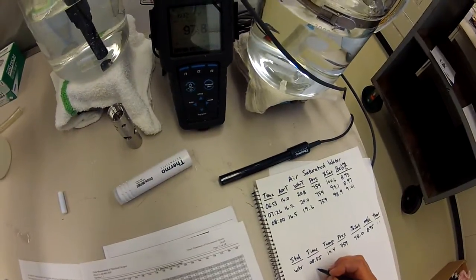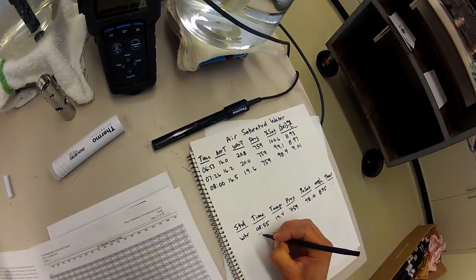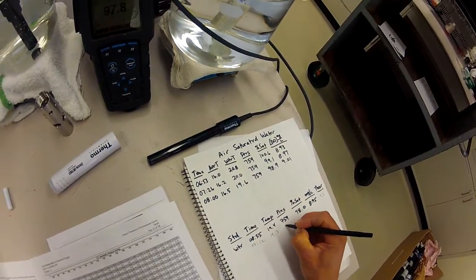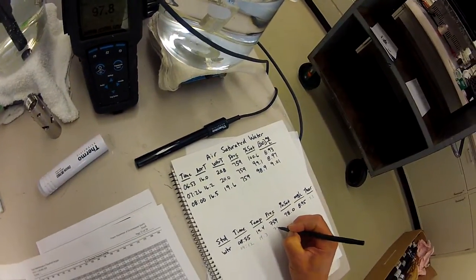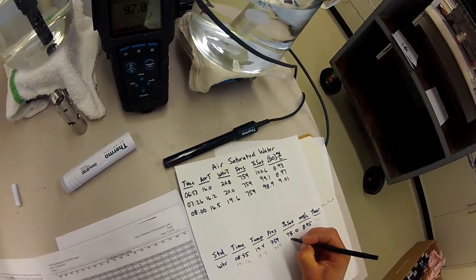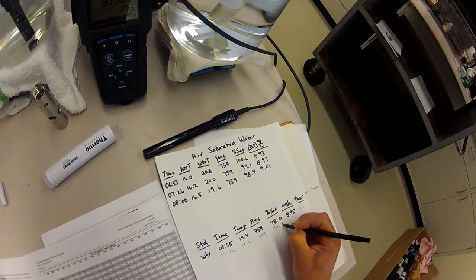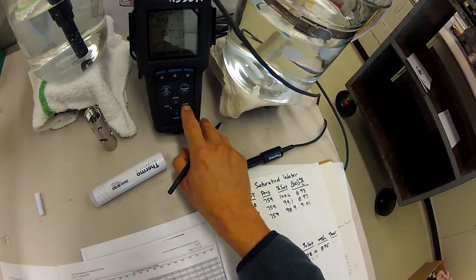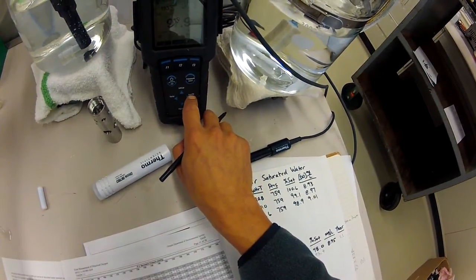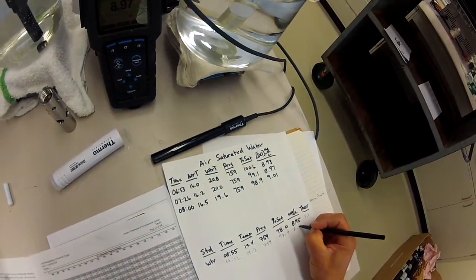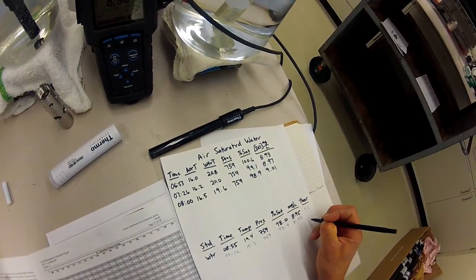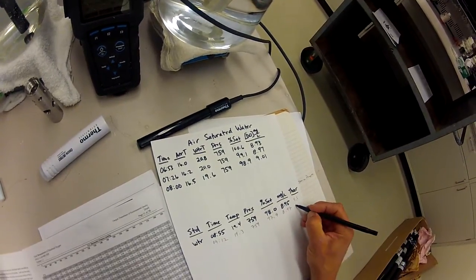Our time is 9:12, our temperature is 19.3, barometric pressure is 759, percent saturation 97.9, and we'll change the mode to get milligrams per liter, 8.97. We've calculated that this theoretical is going to be right around 9.1.